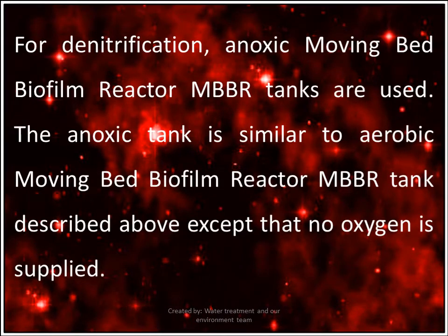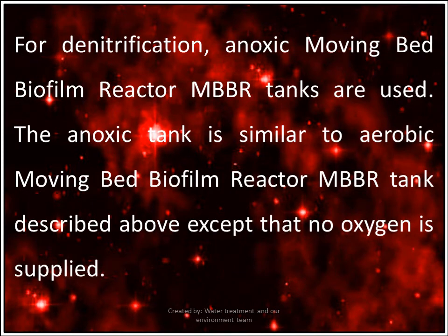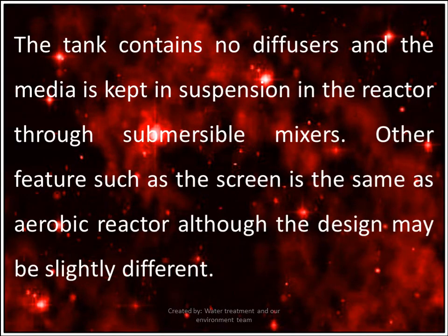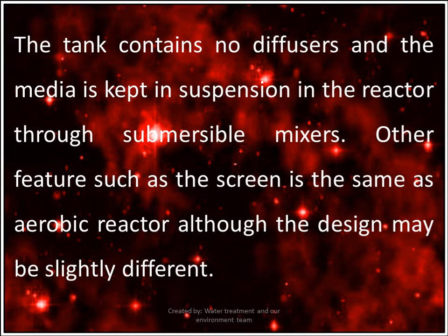For denitrification, anoxic MBBR tanks are used. The anoxic tank is similar to the aerobic MBBR tank except that no oxygen is supplied. The denitrification tank contains no diffuser and the media is kept in suspension through submersible mixers. Other features such as screens are the same as in the aerobic reactor, although the design may be slightly different.